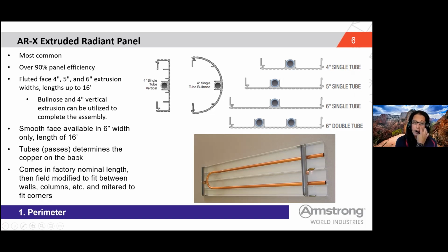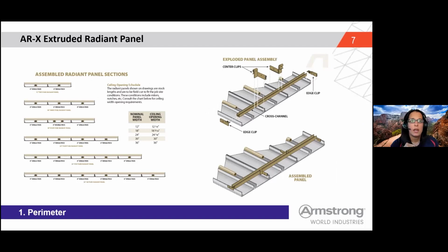So the tubes or passes on the back determines the amount of copper. And this comes in factory nominal length. It ships to the job site, and then it's field modified to fit between walls, columns, and you miter the corners to fit. Go through a little bit more of that installation detail here. So like I said, if you're going to put a couple panels together at different widths, it kind of shows here how you have the different panels connected together with cross channels and edge clips. There's center clips kind of to hold everything together along that length. It shows a fully assembled panel at the bottom. And then, in our catalogs, we have the nominal panel width and the ceiling opening width to keep in mind when you're ordering.